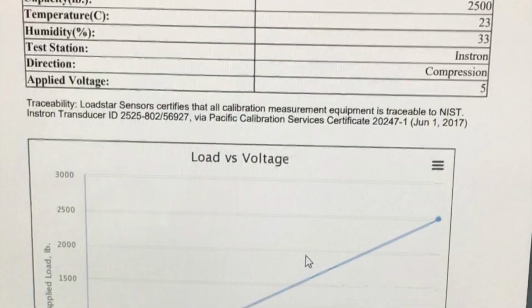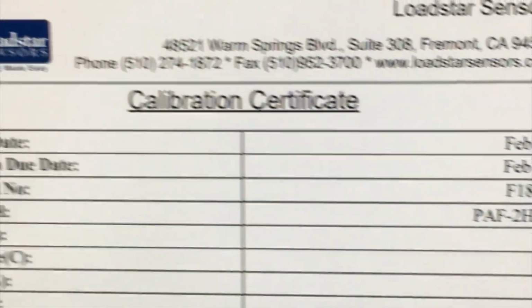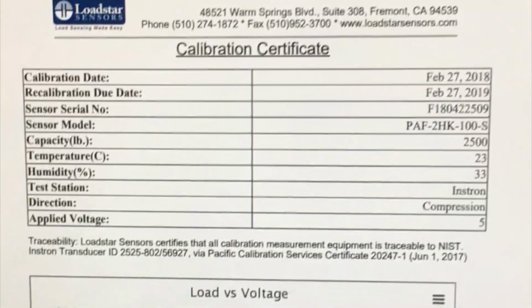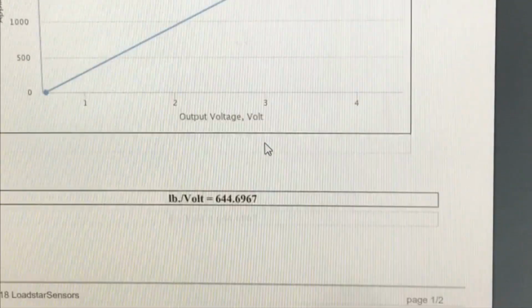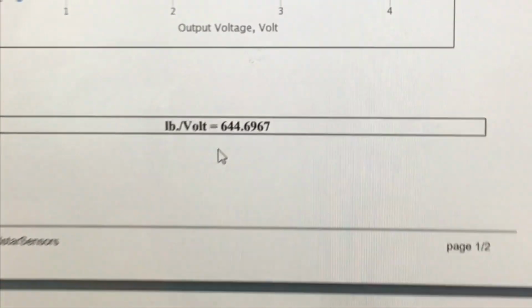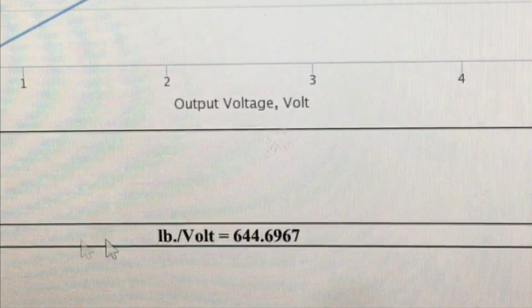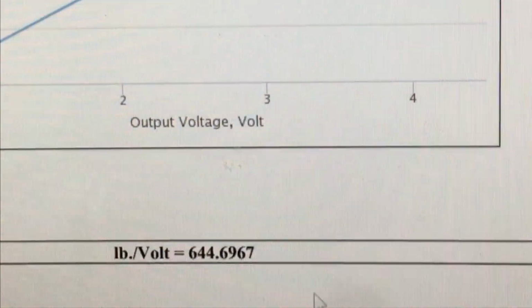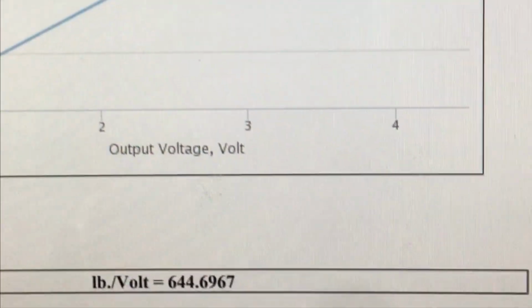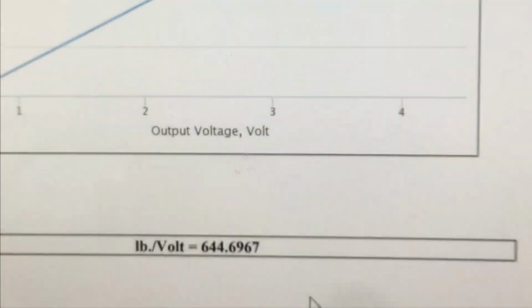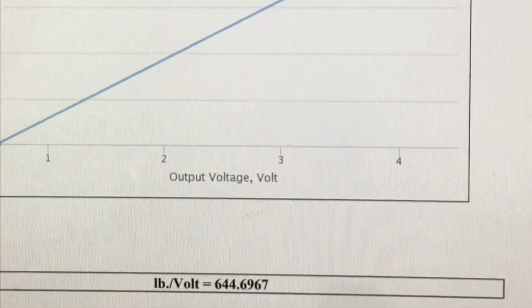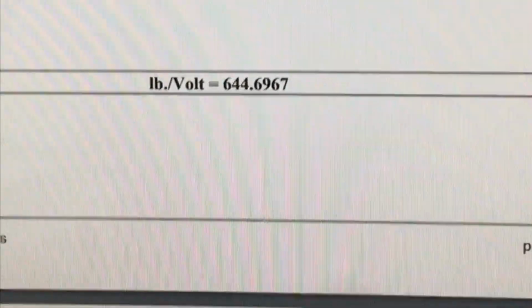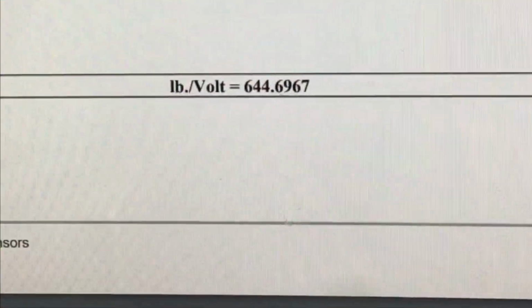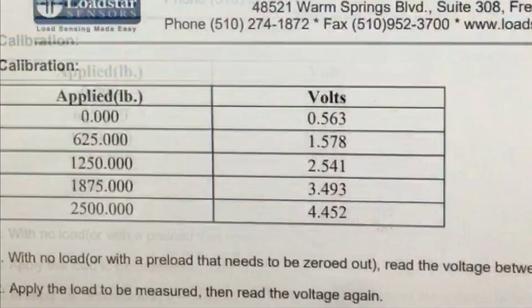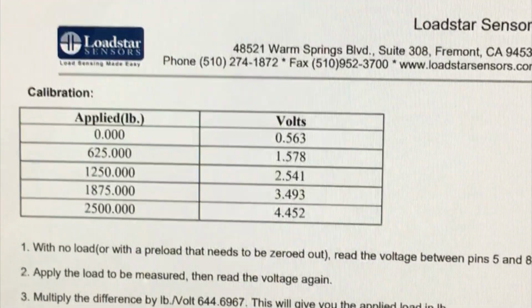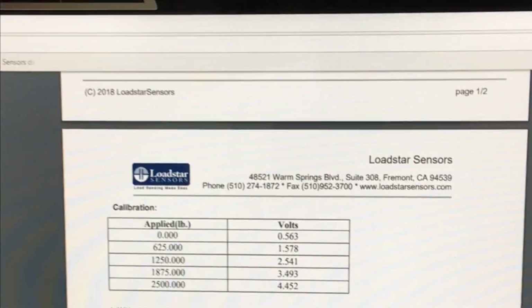So after the calibration is completed, we generate a calibration chart for this particular unit that shows the applied loads and the output voltages for those applied loads. And essentially we get a linear number that you can use to infer your loads from the voltages, which is shown here. So this is about 644.7 pounds per volt. So if you start out with your zero load voltage and figure out the delta from that number, you can just multiply it by this number and you'll get the applied pounds of force on your sensor. So this is what the calibration looks like, and that's what the calibration certificate that you get will look like.